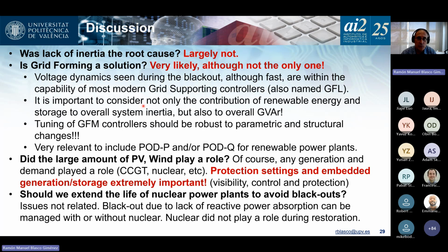It is important not to forget the contribution of renewable energy to the overall reactive power and to the control. Also, in the blackout in the UK in 2019, August, September, one of the issues was some voltage stability issues in Hornsea. So that's something that is going to play a key role in the systems. We have been talking a lot about inertia. Please don't forget voltage. There's very little experience with grid forming controllers, and those grid forming controllers should be robust and not introduce additional issues.